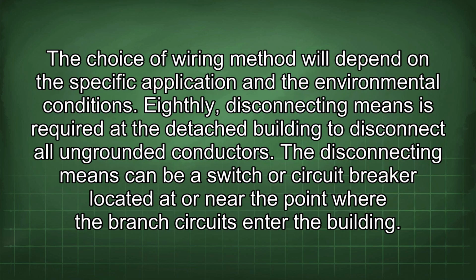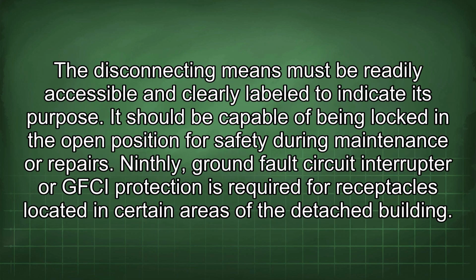The choice of wiring method will depend on the specific application and the environmental conditions. Eighthly, disconnecting means is required at the detached building to disconnect all ungrounded conductors. The disconnecting means can be a switch or circuit breaker located at or near the point where the branch circuits enter the building. The disconnecting means must be readily accessible and clearly labeled to indicate its purpose. It should be capable of being locked in the open position for safety during maintenance or repairs.